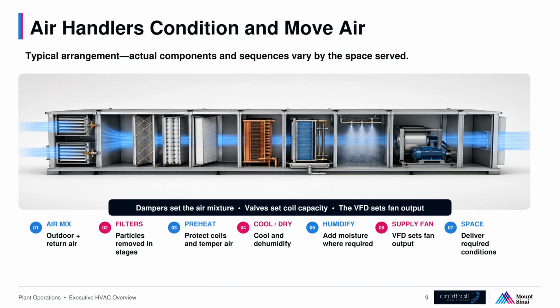The air handler is where plant capacity becomes conditioned air. A typical mixed air unit combines controlled outdoor air with return air, then moves the air through filters. A preheat coil tempers very cold air and helps protect downstream components. The cooling coil lowers the dry bulb temperature and, when its surface is below the air's dew point, condenses moisture for dehumidification. A humidifier adds moisture where the space requires it, and the supply fan moves conditioned air through the duct system. The fan VFD adjusts output to system demand, while dampers and coil valves regulate air mixture and heating or cooling capacity. Not every air handler contains every section. Critical care, isolation, and laboratory systems may use different outside air, filtration, exhaust, redundancy, and control arrangements. The actual approved sequence governs how each unit must operate.